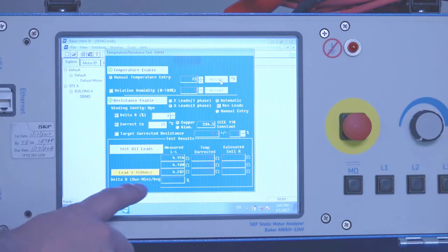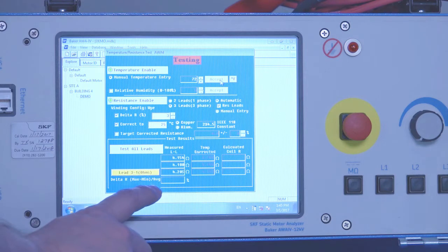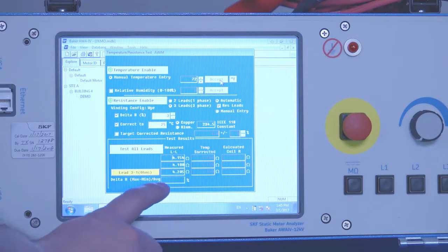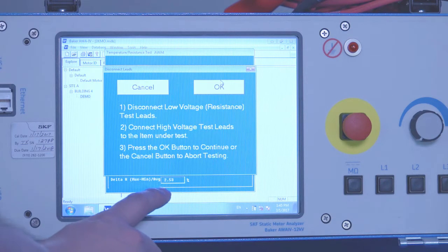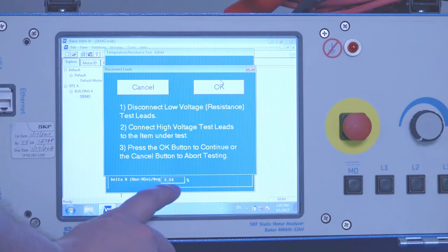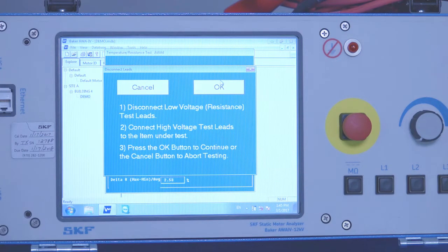It's going to calculate the difference in resistance as a percentage. It's going to use this particular equation that you see here to calculate this resistive imbalance. In this case a 2.53% resistive imbalance.